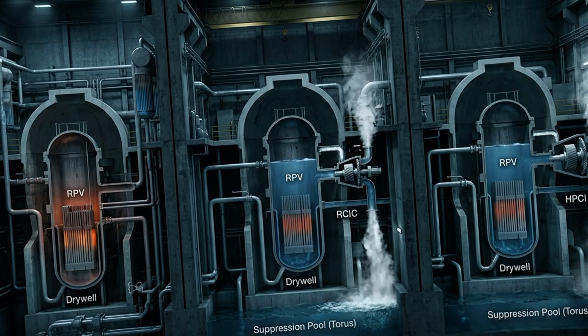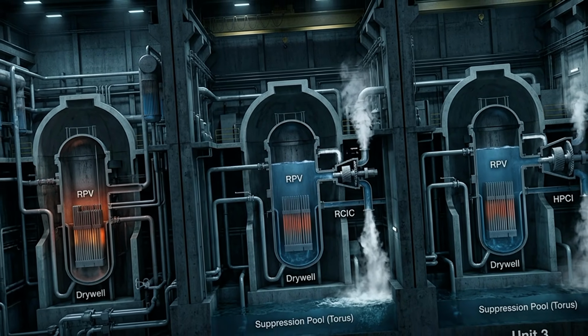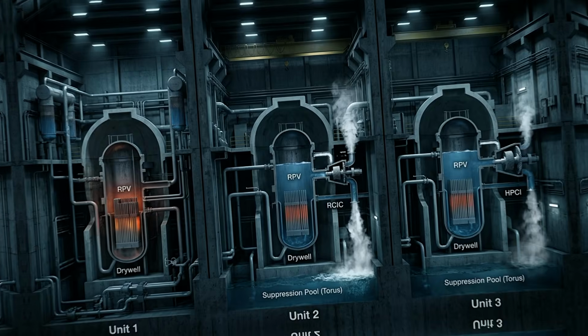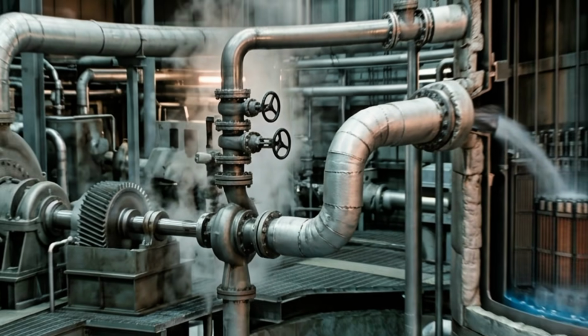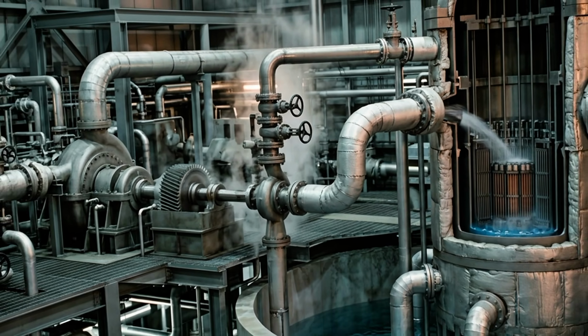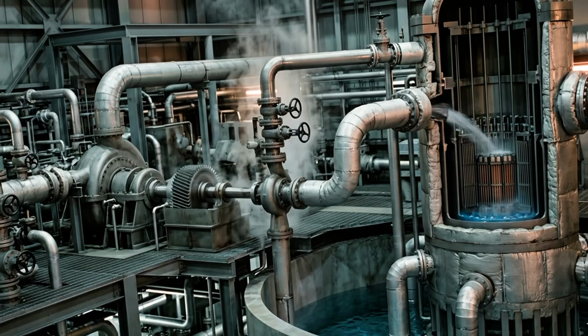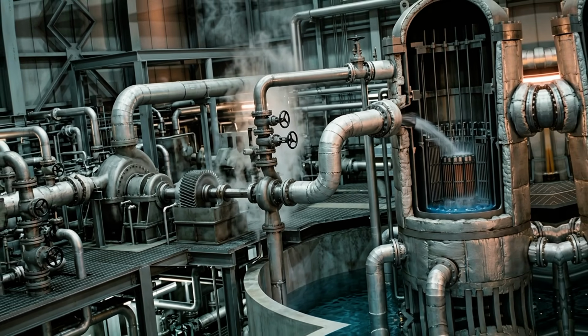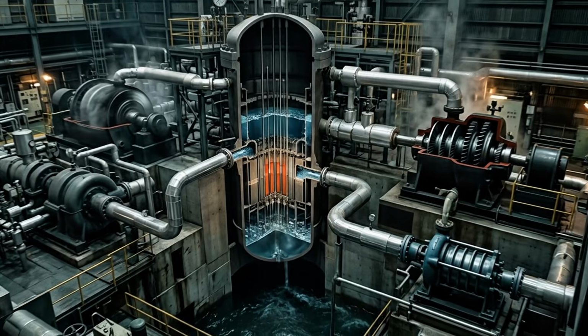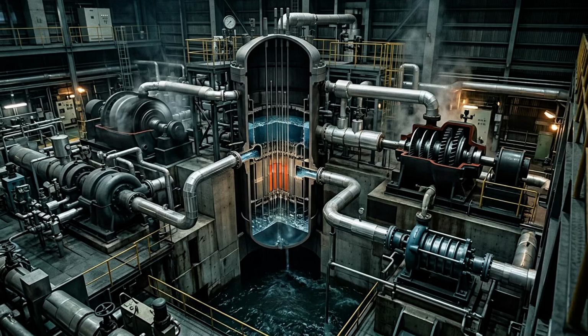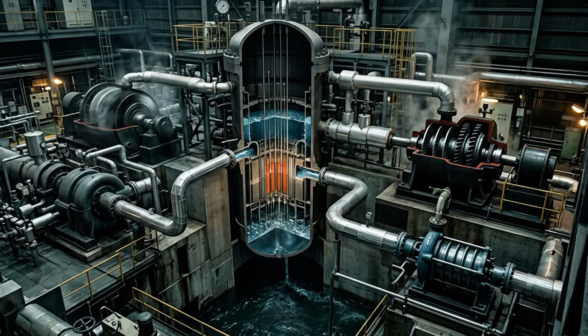Units 2 and 3 followed different paths. Their emergency cooling systems continued operating much longer. Steam-driven systems such as reactor core isolation cooling provided valuable periods of cooling without relying entirely on normal AC power. Unit 3 also used its high-pressure coolant injection system for a period.